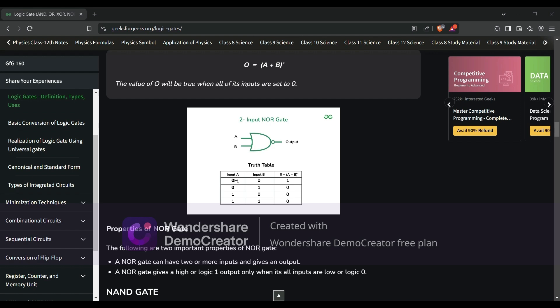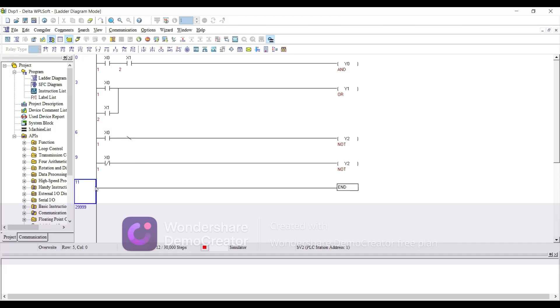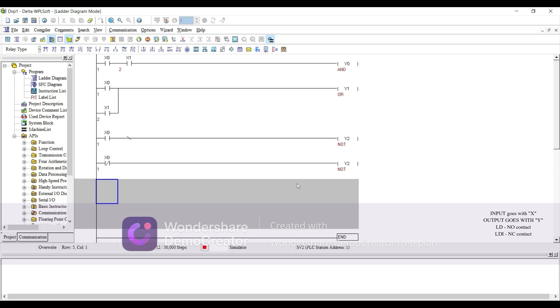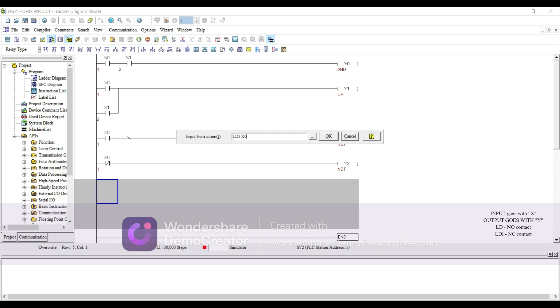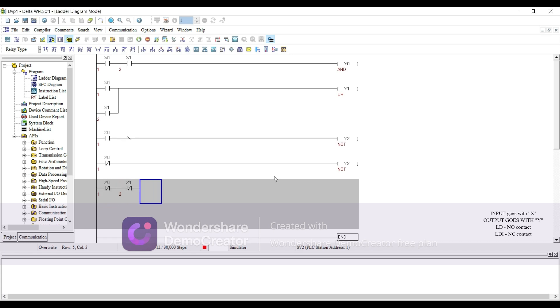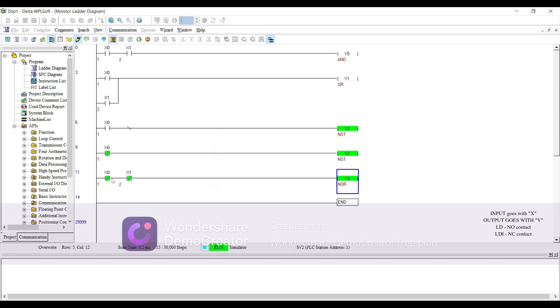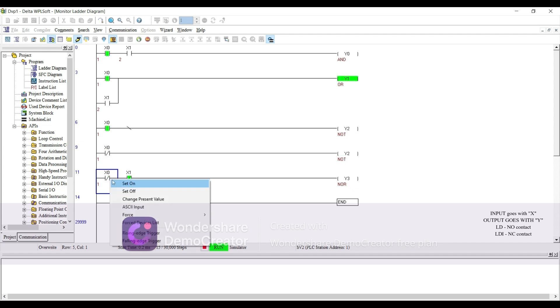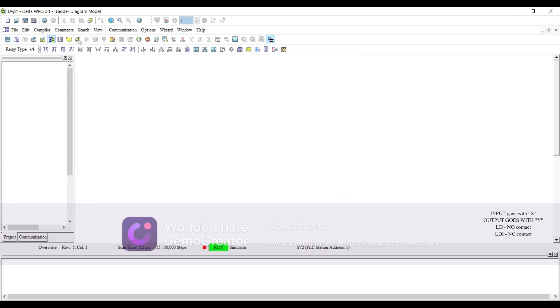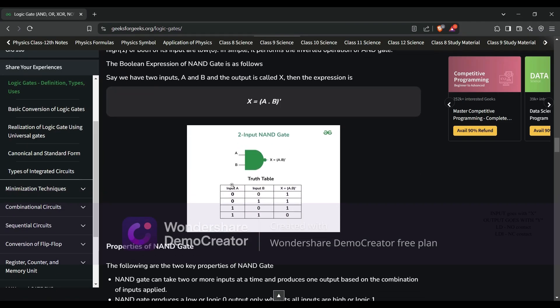Now we have NOR gate. In NOR gate, if both inputs are off you have an output; if you have one input, or the other, or both on, you have no output. Let's try it: LDI X0, another LDI X1, and OUT Y3 — this is our NOR gate. Go online: both inputs are off, we have an output. If I turn one on, we do not have an output.